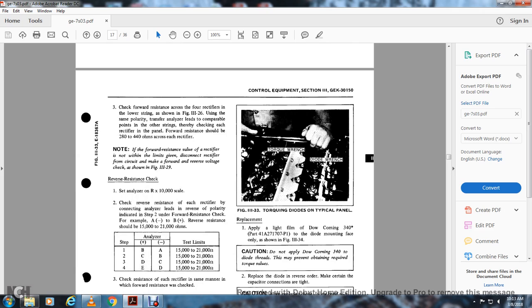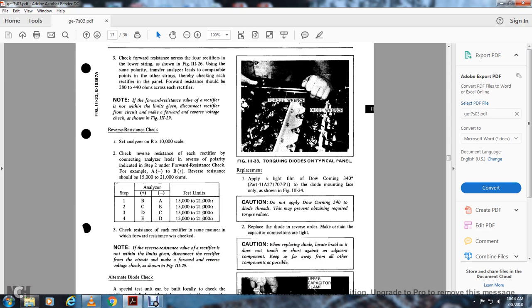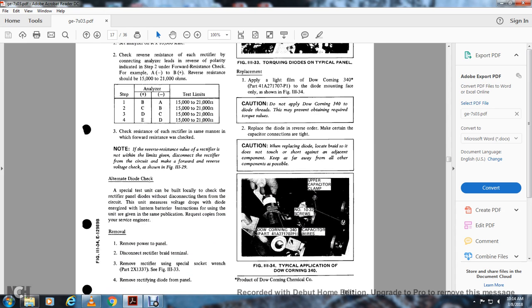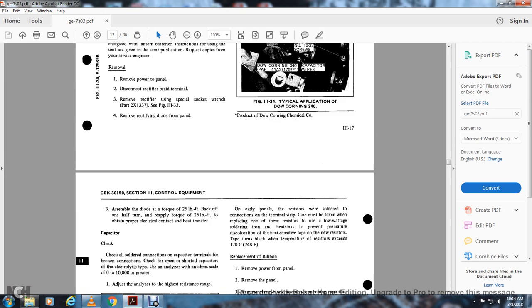Figure 333, torque of the diode within the typical panel. Use the torque wrench and the diode wrench for replacement. Apply a light film of Dow Corning 340. Diode mounting, see figure 334. Caution: do not apply Dow Corning 340 to the diode thread, to avoid preventing the required torque values. Replace the diode in reverse order and make sure the capacitor connections are tight. Caution: when replacing the diode, locate the braid so that it does not touch or short against adjacent components. Keep it as far away from all other components as possible. Figure 334, typical application of Dow Corning 340, with capacitor wire, number 10-32 screws, and upper capacitor clamps.